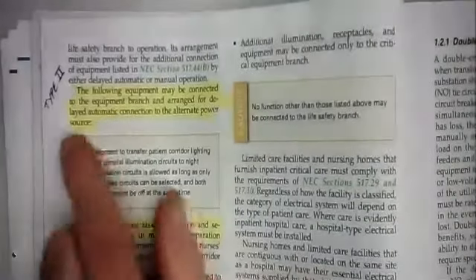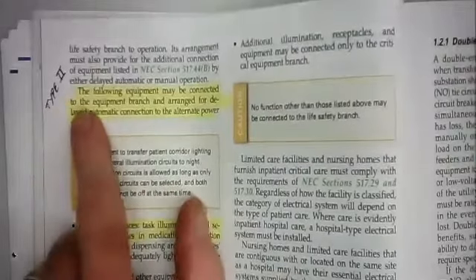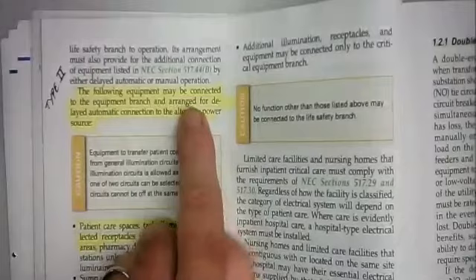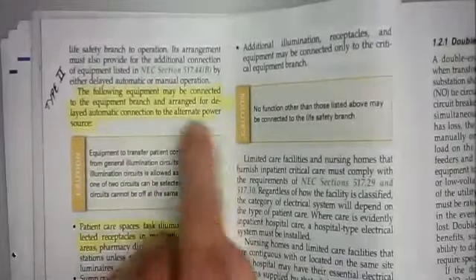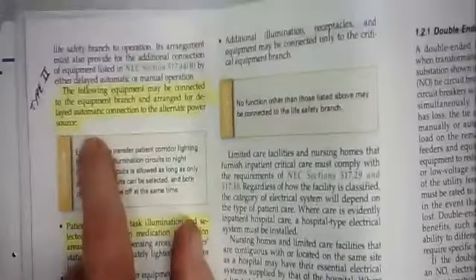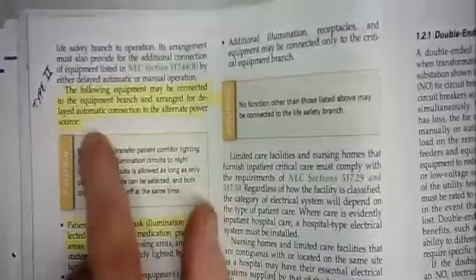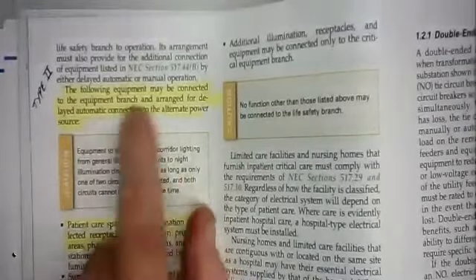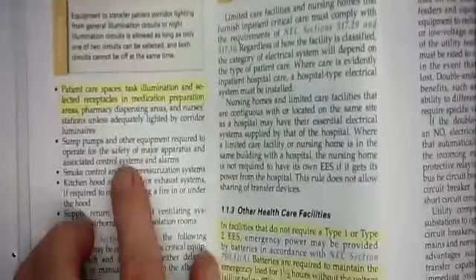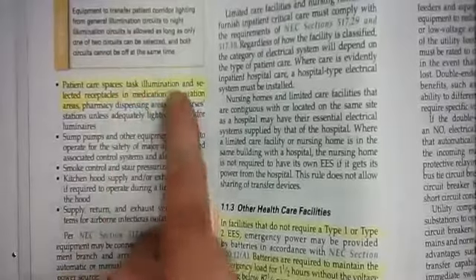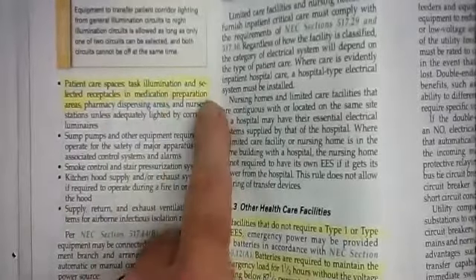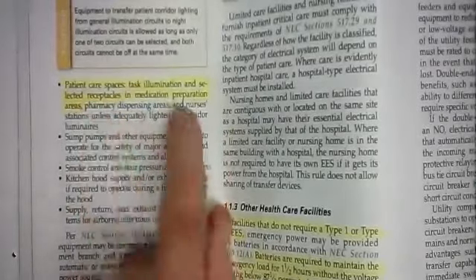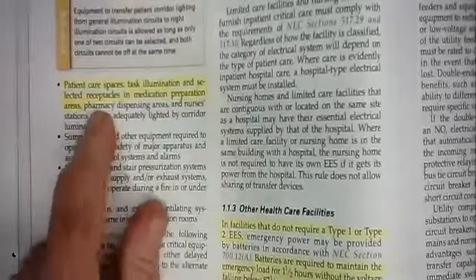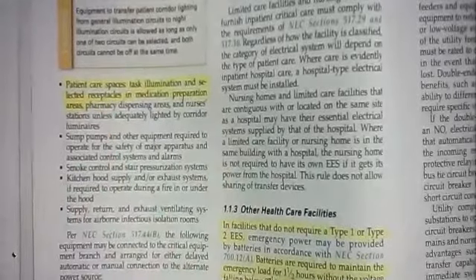I wanted to highlight that just because it's over on page 6, but they're talking about a type 2 EES, and I even wrote type 2 here on page 6, left-hand column. It says the following equipment may be connected to the equipment branch and arranged for delayed automatic connection to the alternate power source. So this equipment is not specifically for preservation of life. So there can be a delay in the switching over to emergency power. Patient care spaces, task illumination, and selected receptacles in medication preparation areas. So for those types of loads, there could be a 30-second delay in switching over to emergency power, and no one would come to any harm.